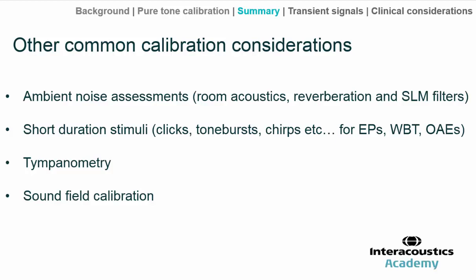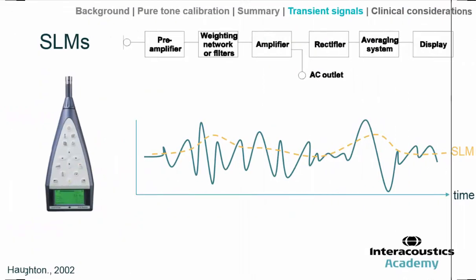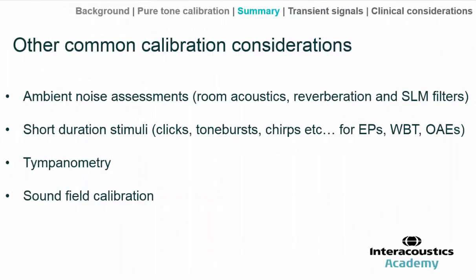Traditional tympanometry involves not just pure tones, but also the pump and microphone that would be calibrated. For sound field testing, there's a series of reference equivalent threshold sound pressure levels available for different incidences, like straight ahead or off to one side. Warble tones are typically used to prevent standing waves from forming, and we'd typically use a different microphone attached to the SLM than the ones used in the coupler. In principle, the information we've learnt so far is very transferable to these different applications.